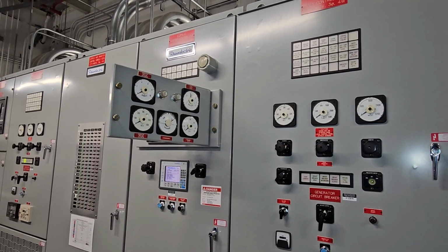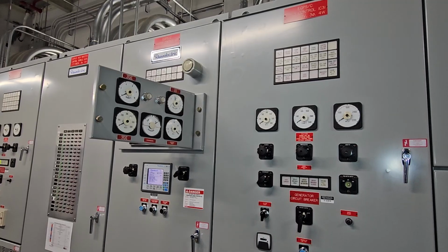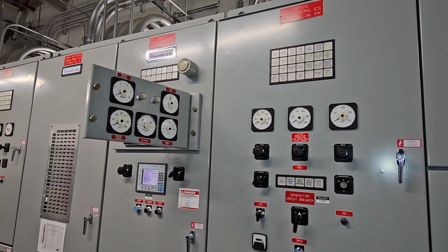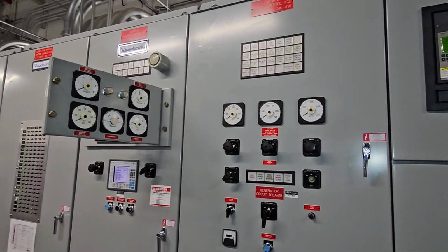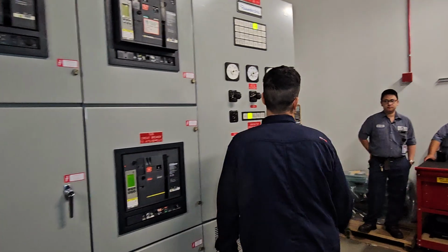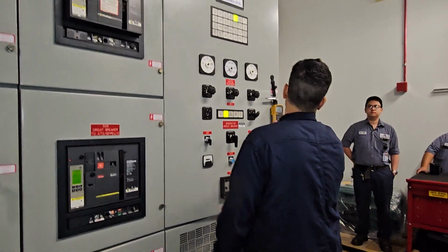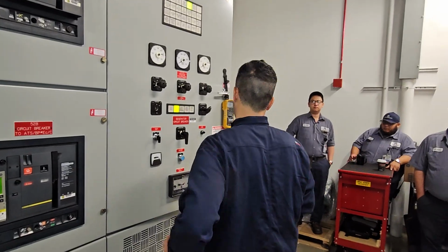Okay, give it a second. This is 200 volts. This is just for my reference, but I can switch here to hertz. I'm at 60.01, which is pretty good. So I just record those numbers for myself to compare with the other generator.